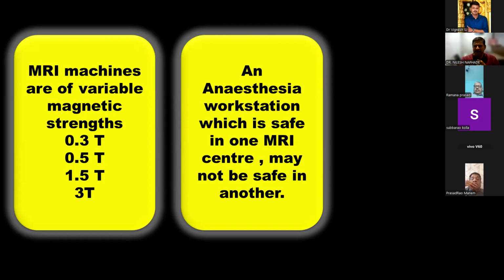I want you to know this. You need to be aware whether this MRI machine and that MRI machine are the same. If the MRI machine in this center is 3 Tesla, and the MRI machine in the other center from where the anesthesia machine is being brought is 1.5 Tesla, that machine will get sucked into this 3 Tesla machine. So a machine which is suitable for a 1.5 Tesla machine may not be suitable for a 3 Tesla machine.